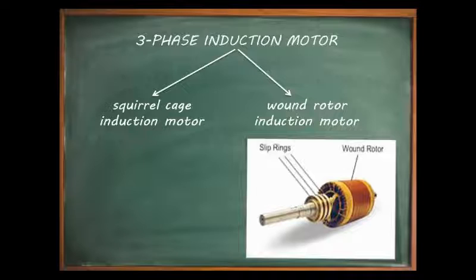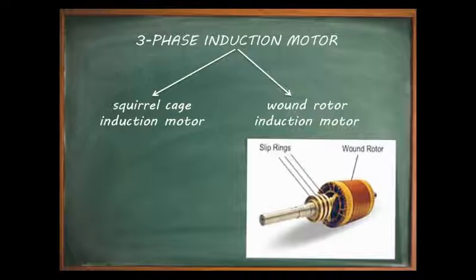Wound secondary rotors are often called slip ring induction motors. Slip ring induction motors are less extensively used compared to the squirrel cage induction motor because of their higher first cost and greater maintenance cost. They are used only when speed control or higher starting torque is required, due to the facility of adding external resistance in series with the slip ring.